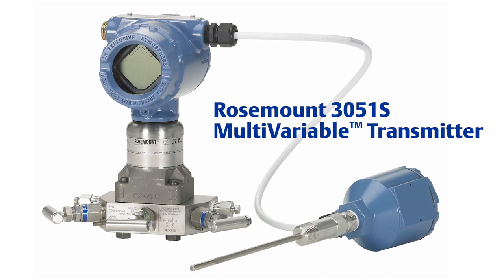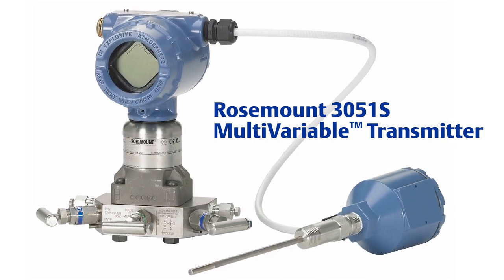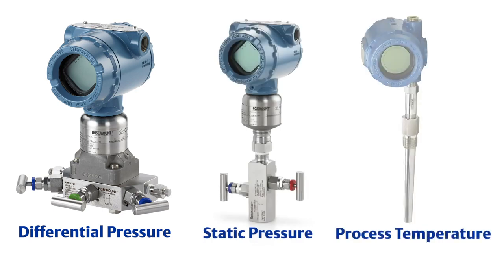The calibration of Rosemount's multivariable transmitter is comparable to individually calibrating differential pressure, static pressure, and process temperature transmitters. It's important to note that Rosemount products need a zero trim calibration after initial installation to negate any mounting effects. And a full field calibration is necessary only if the transmitter is found to be out of specification. In this video, we will walk through the manufacturer's recommended steps to accurately and safely perform a full field calibration.